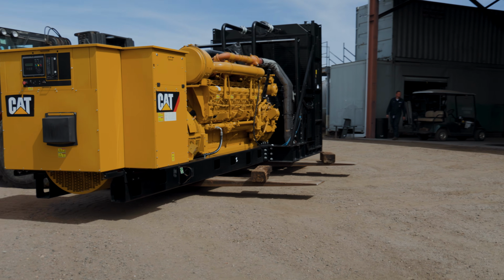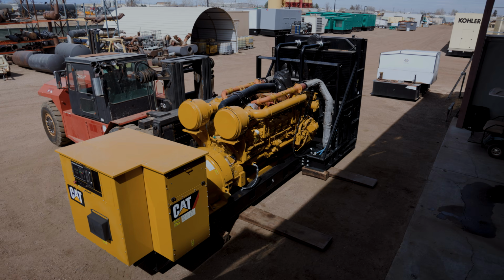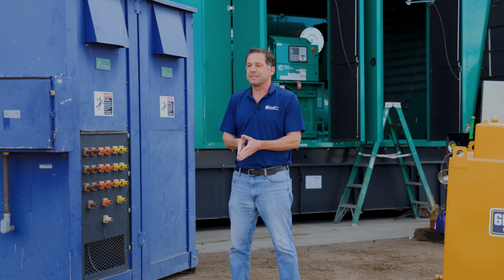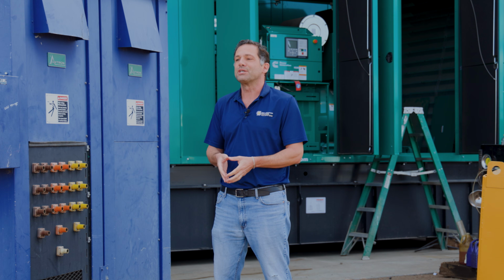We've had customers call in and say that their engine is leaking oil out the side of it, and upon arrival we realize that it's not oil, it's literally raw diesel fuel just dripping out of the exhaust manifolds. A load bank is a piece of equipment that allows us to simulate a load on the generator that it would experience during an outage.